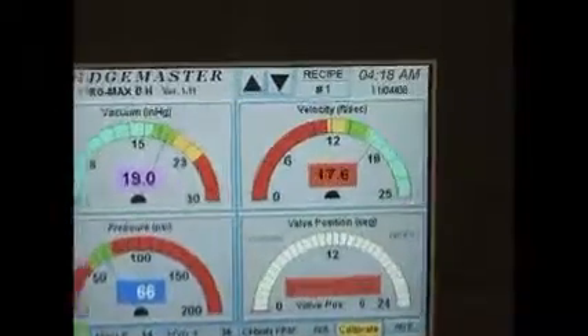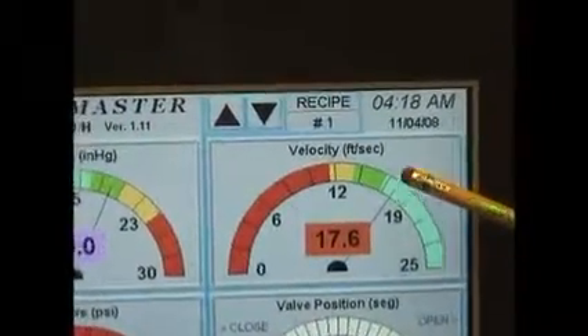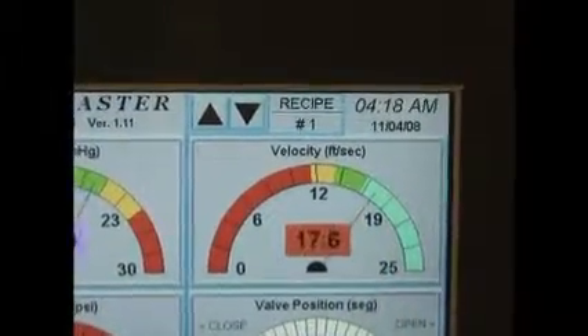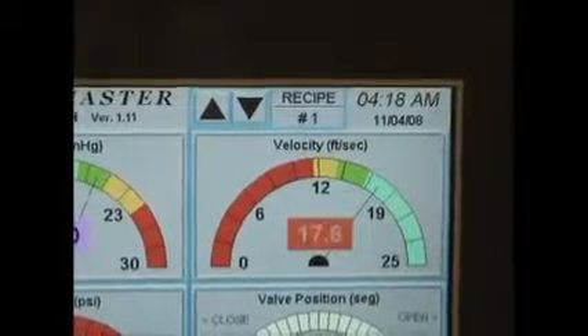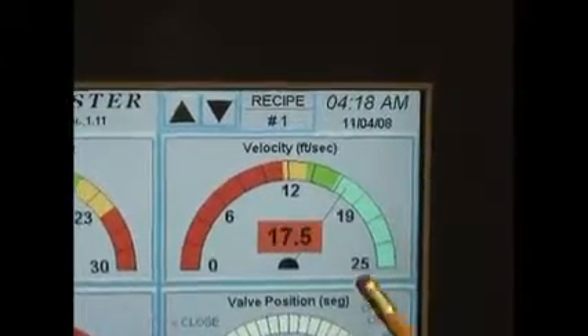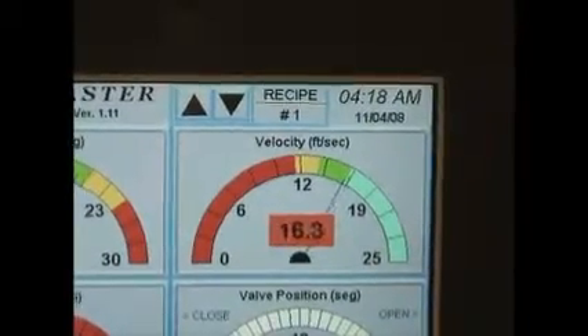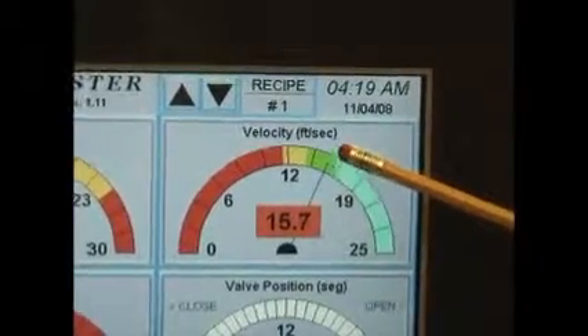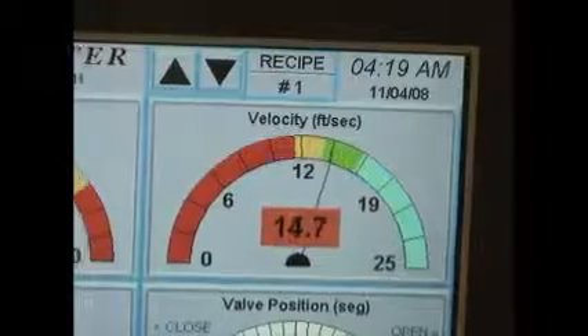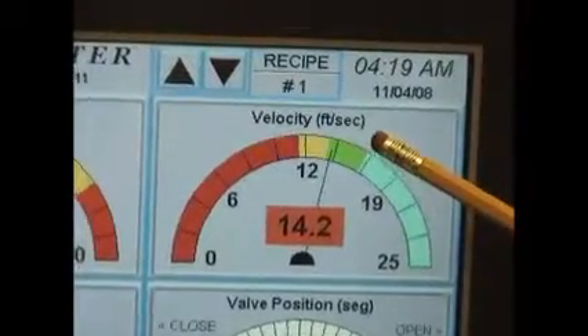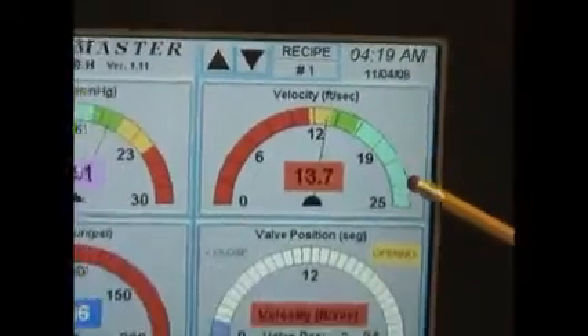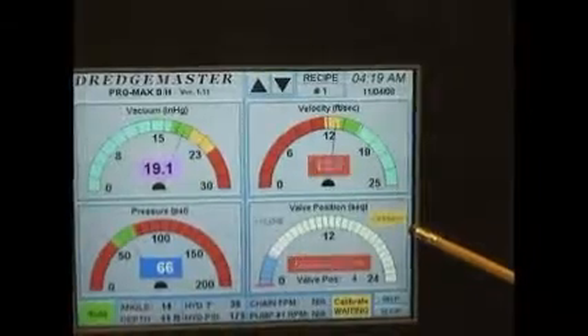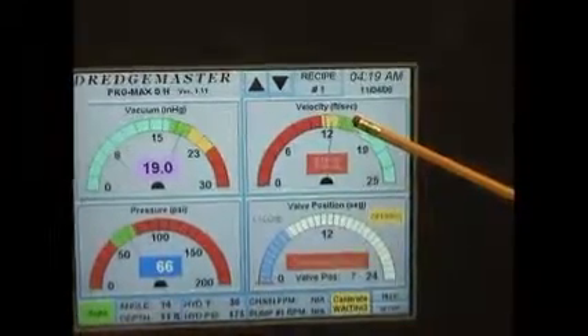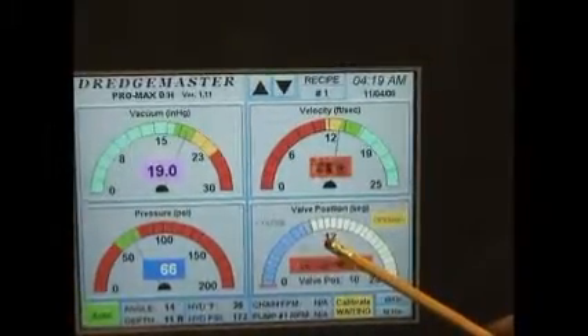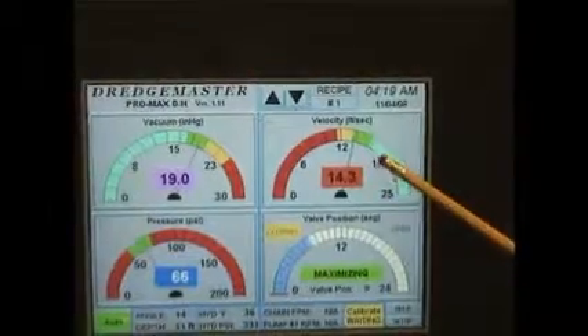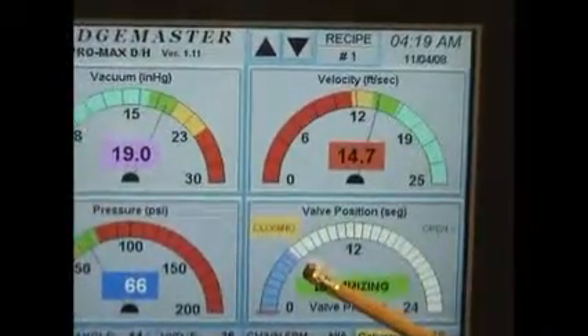The velocity also represents 4 colors. As we explained before, the turquoise represents low production, the green is good production, the yellow is caution, and the red area is starting to get yourself into serious trouble. As our velocity starts to slow down, we have more material or a high percent of solids in the pipeline. In our green zone area, of course, the valve remains closed. Once the material starts slowing down in the pipe and we enter into the yellow zone, we are now starting to open up the valve. The valve is opening. We're in the yellow zone here. Once we get enough fresh water introduced into the pipeline, our velocity starts speeding up. We're back into the green zone. We can now start to close our valve back.